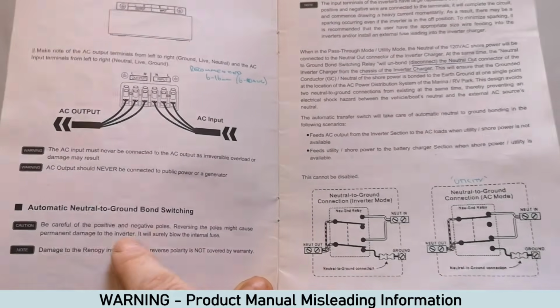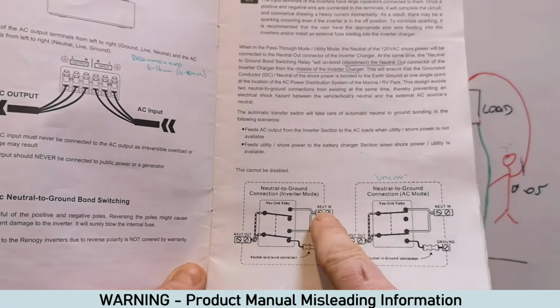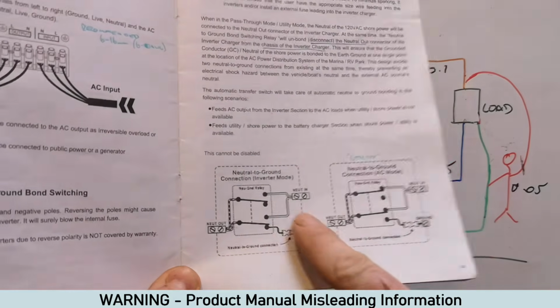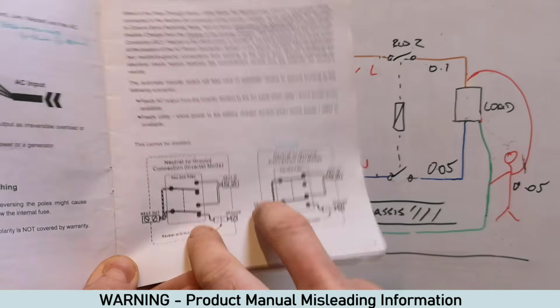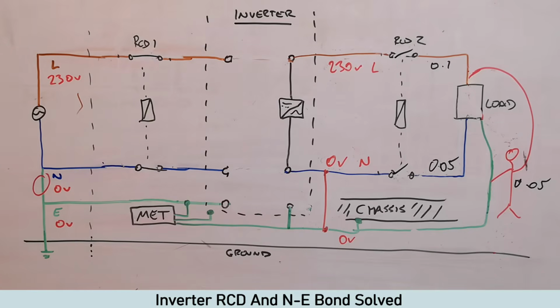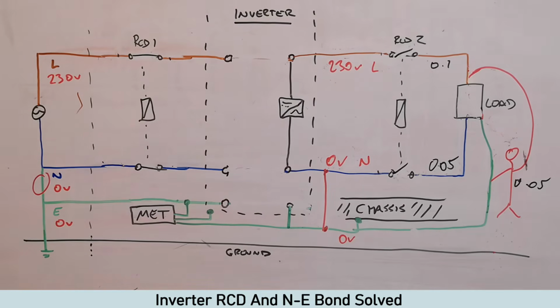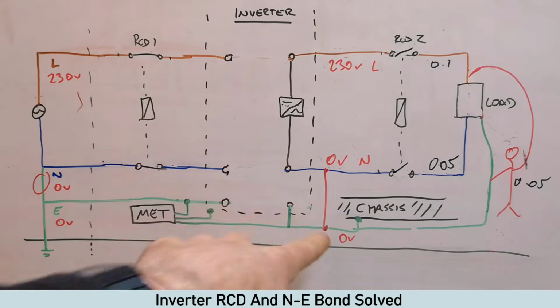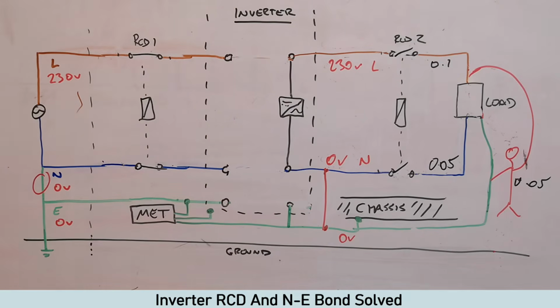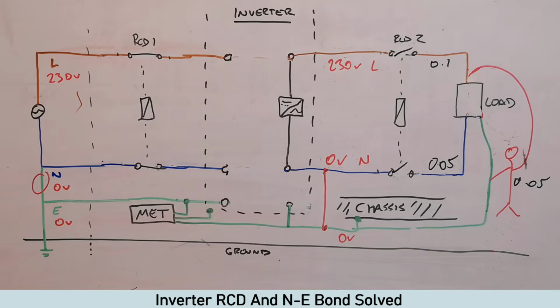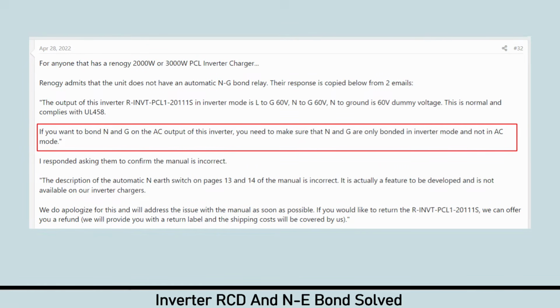So obviously there's an automatic neutral to ground bond switch in the manual that isn't in the inverter. So you think you're installing this for an RCD to work, which it will if this is installed, but you're not getting this, which is an issue. I've been to and fro with Renogy for quite a few months now, which is why it's taken so long to do this part 2. Almost every reply has told me that you can't neutral to earth bond the Renogy PCL inverter charger. I've been on forums looking around, and I found a forum, I'll show you here now, where someone has actually been in touch with Renogy, and they have stated you can do it.